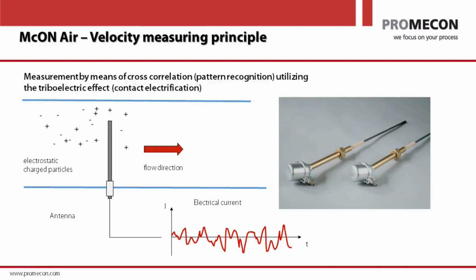If you have a duct, you can see the two blue lines that describe this duct here. You put our sensor in. Our sensor is acting like an antenna that can pick up electrostatic charge. Why do we have electrostatic charge? We have ash particles going through the duct, and these ash particles are always charged if you have a hot gas. Where does this charge come from? The particles have friction against the gas, against themselves. These small particles have a huge surface, so that surface charges up. I wouldn't say it's exactly like in a thunderstorm, but it's a similar mechanism.